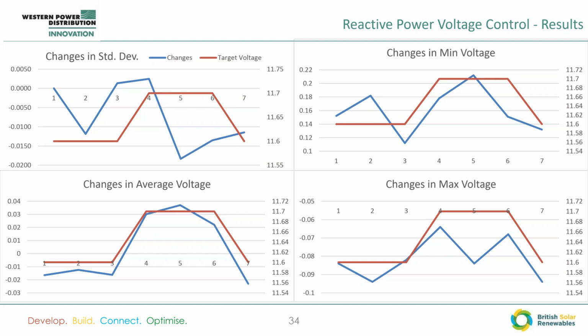So we're looking for changes from the standard overnights to the test nights. And we were able to have a very small influence on the changes in the average voltage. So overnight, usually it was around 11.66. So when we set it to 11.6, we were able to reduce the voltage slightly. When we set it to 11.7, we were able to raise it slightly. And so the change in the average voltage, we're seeing a pattern there of some effectiveness.